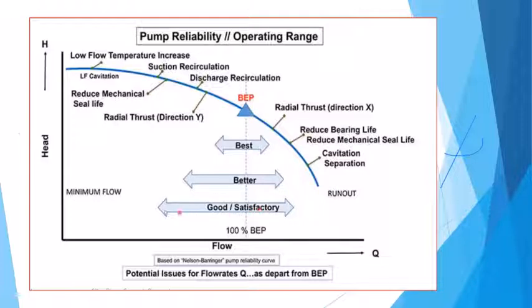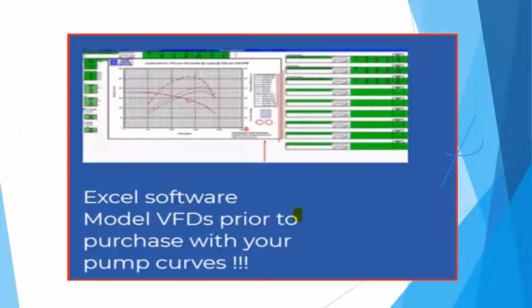There's also satisfactory ranges of where it's best to actually run that, because as you can see, there are certain points you've got to be watching: suction, low flow temperature increases, reduce mechanical seal life, radial thrust direction, all those mechanical issues that are happening inside, the amount of lift and pressure. So when you put various types of starting and controlling technologies onto a given motor, you want to be careful where we're at.